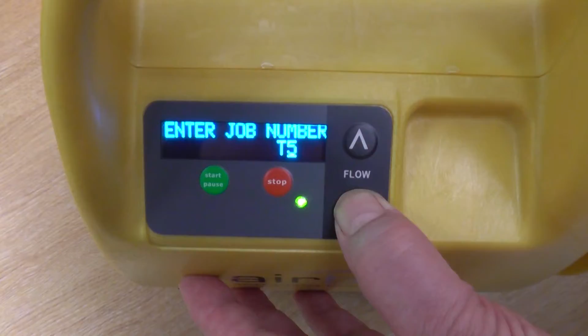Once you press the capacity test green button, it allows you to enter the amount of air you want to collect. I'm going to change the 480 litres to 960 to demonstrate. So we're going to enter, enter, and then increase the 480 to 960. Enter, enter, enter. We're going to collect it at 8 litres. You can collect at 16 by changing the buttons. And then you can again have a logging period of either 1 second, 60 seconds, or 30 seconds for your data output. We're going to log at 1 second.